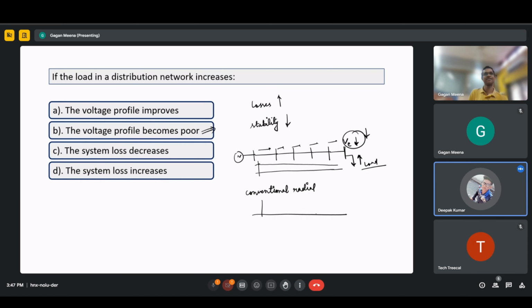I think it is possible when a leading power factor load is connected. Yes, that is possible. But generally most of the loads are lagging loads. So we use capacitor banks for that, industrial consumers generally use them, or big residential homes might use them. But normal household consumers have lagging loads and they don't use capacitance, so the voltage is less than the substation voltage.